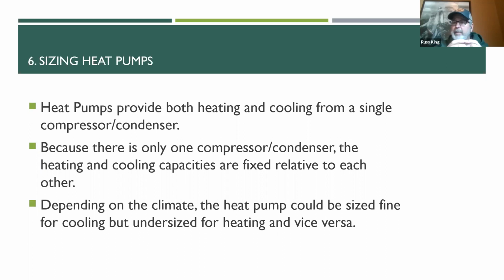And depending on your climate, it could be fine for your air conditioning, but too small for your heating, or fine for your heating and too small for your air conditioner, or something like that. So there's a limitation there. So you have to be more thoughtful in how you size your equipment. And don't ever forget that you can always change the load of your house. You can always improve your house to make it different. Okay. So if it seems like a heat pump doesn't fit, you should always consider changing the house, changing the load. Don't always focus on the supply, the capacity of the equipment. Also think about the ability to change the demand of the house.